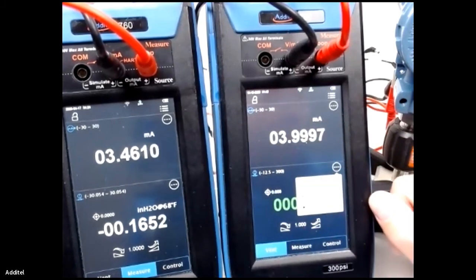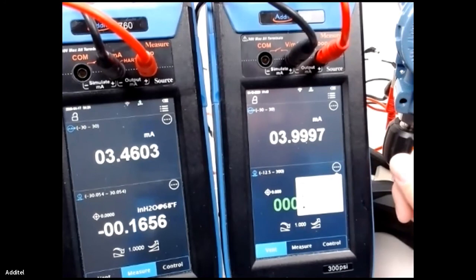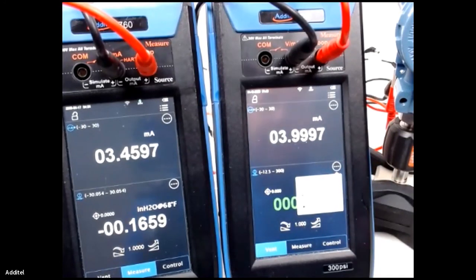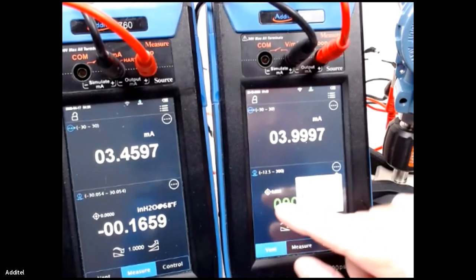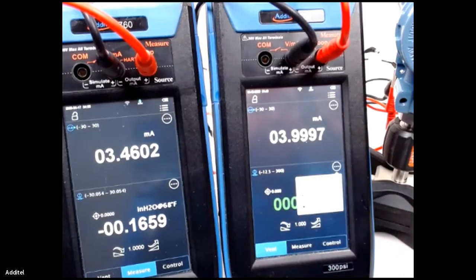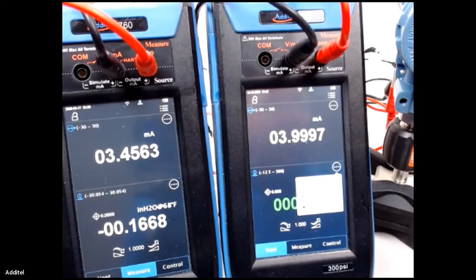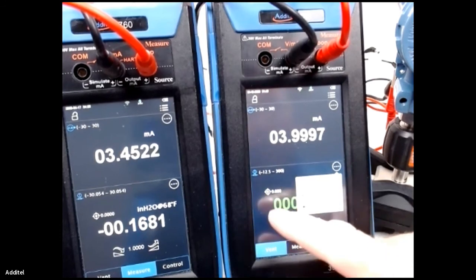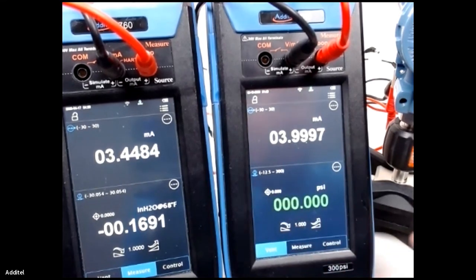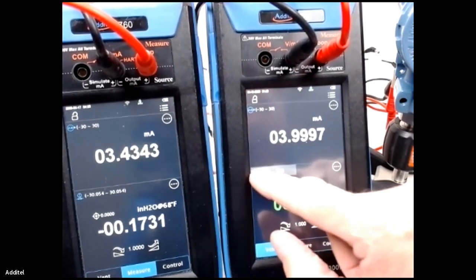There's also an auto step feature in here, which is kind of cool. So if you're going out in the field and you want to do a step, so you want to set it at 0, then 50, then 100, it will step through that, and you can set the time that you want it to stay at each of those pressures before it goes to the next one. I'm not sure we're going to do that right now, but I did want to let you guys know that that's available in the module.